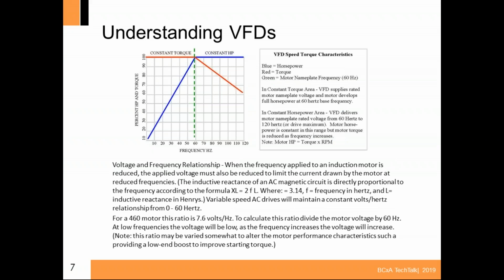When VFDs speed up, they're sized to go to 60 hertz. As you can see from this graph, our percentage horsepower and torque increases. We have a constant torque until we get to 60 hertz. Once we get past 60 hertz, we maintain constant horsepower and we start dropping torque. When you get the PowerPoint presentation in the PDF, read the bottom of this a little closer, and I'd recommend trying to get a handle on all this. It took me a while to understand it, but for some people it's like, yeah, it makes total sense, I've known this for 20 years.